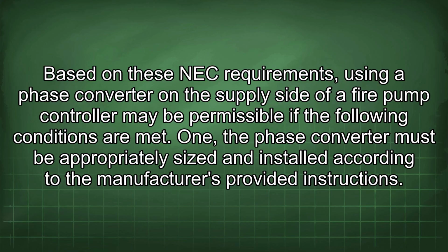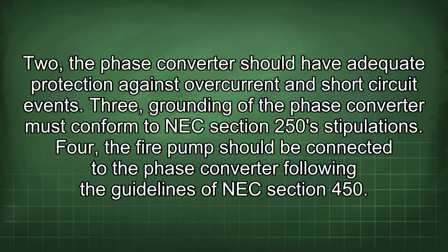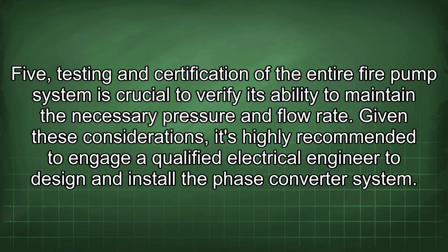1. The phase converter must be appropriately sized and installed according to the manufacturer's provided instructions. 2. The phase converter should have adequate protection against overcurrent and short-circuit events. 3. Grounding of the phase converter must conform to NEC Section 250 stipulations. 4. The fire pump should be connected to the phase converter following the guidelines of NEC Section 450. 5. Testing and certification of the entire fire pump system is crucial to verify its ability to maintain the necessary pressure and flow rate.